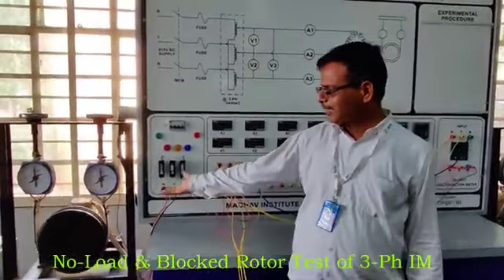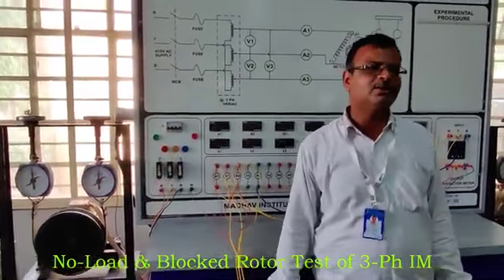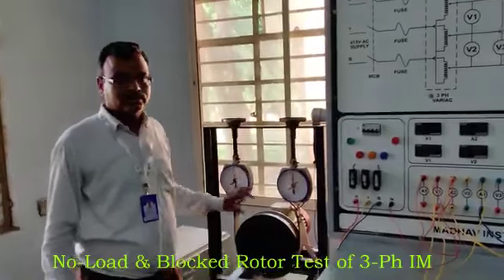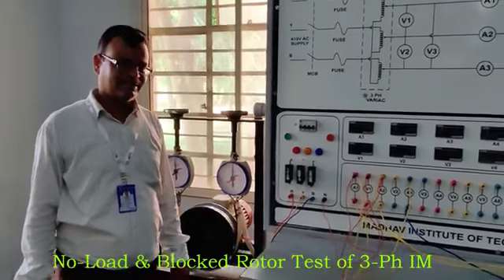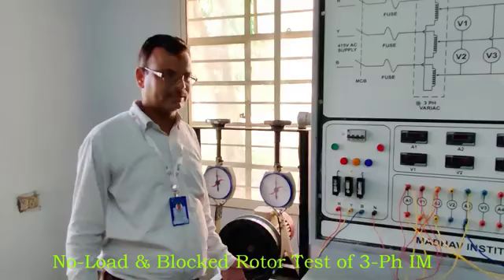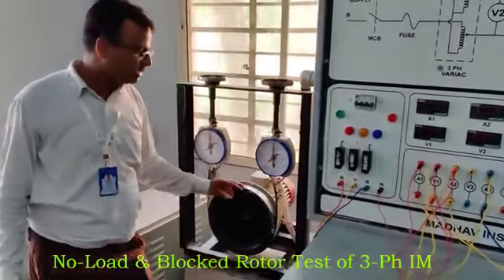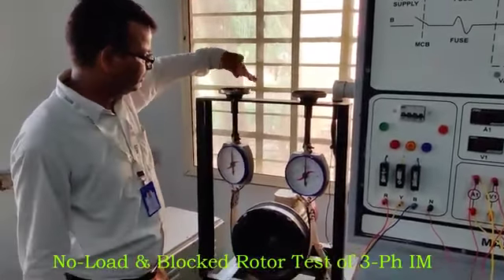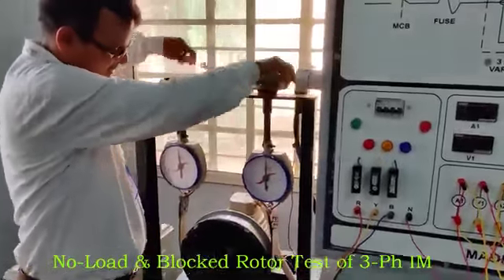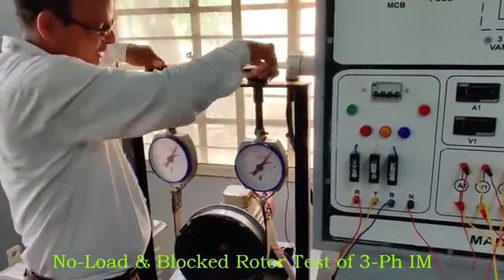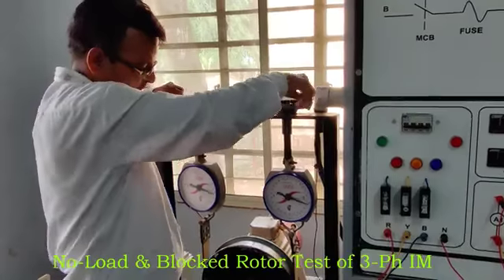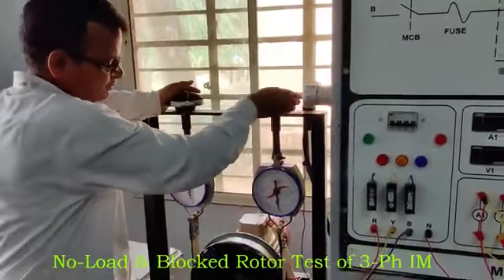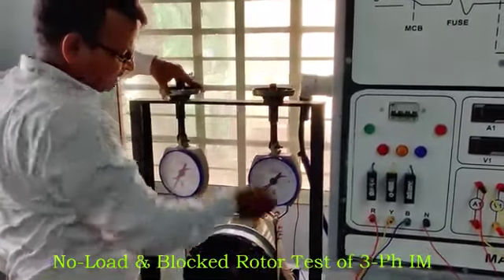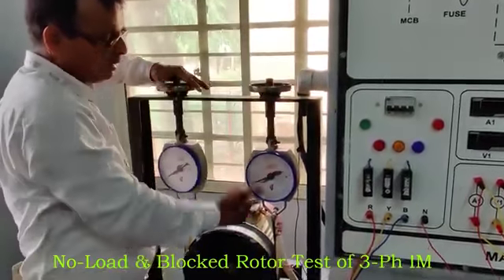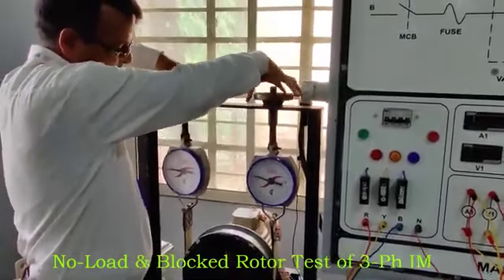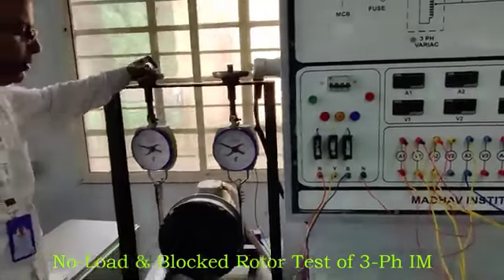And wait for the stopping time of this motor, and then we will perform the second part of this experiment, the blocked rotor test. Blocked rotor test means the rotor is blocked, it will not rotate. We have to tie it with the help of this pulley. Then how to block it? With the help of this mechanical load, tighten the belt in such a way that the motor will not move. Tightly tight. See that it is not rotating. It means it is blocked. That's why it is called the blocked rotor test.